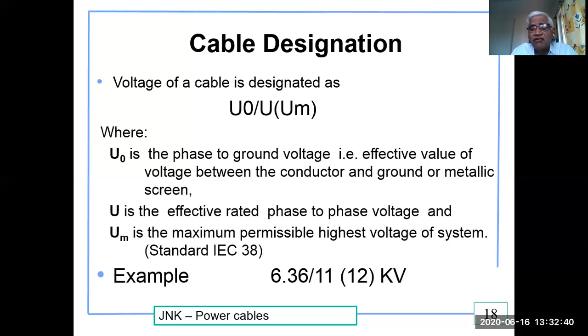The example you can see is an 11 kV cable. The first one is 6.35, that is U0, and the next U is 11 kV line to line. Whatever is given in the bracket, 12 kV, is the maximum that the cable can carry or supply can go. Insulation thickness: now you can see U0, Um, BIL and thickness of the insulation.